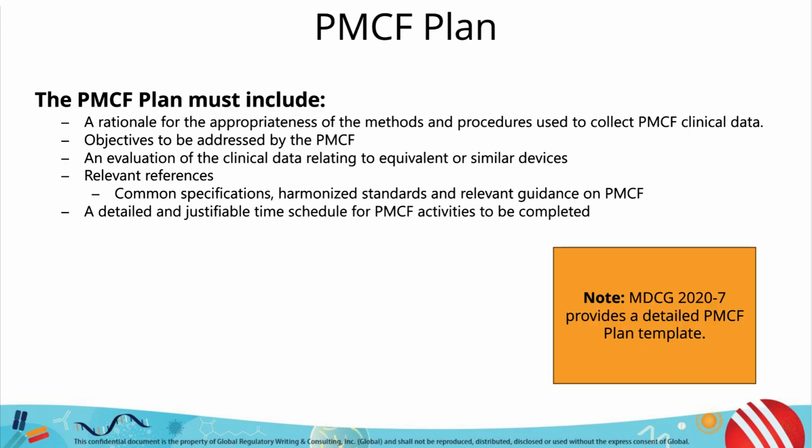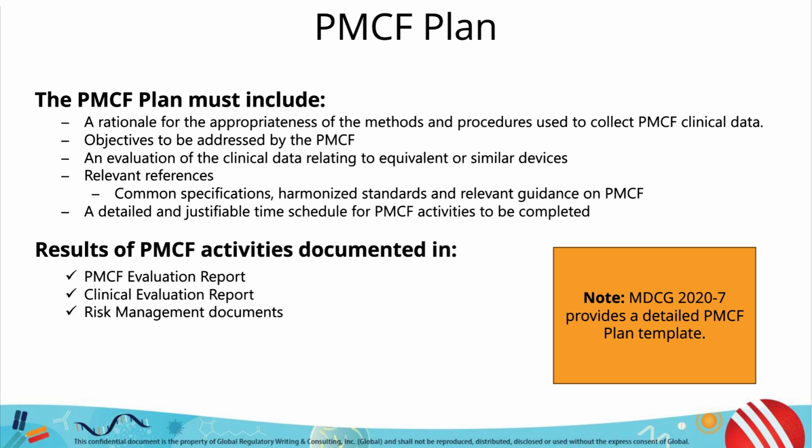The PMCF plan must include a rationale for the appropriateness of the methods used, objectives to be addressed by the PMCF, a plan to capture and evaluate clinical data relating to equivalent or similar devices, relevant and appropriate references, and a detailed and justified time schedule, particularly as it relates to the expected device lifetime. The results of these activities feed into multiple documents, such as your PMCF report, your CER, and risk management documents.